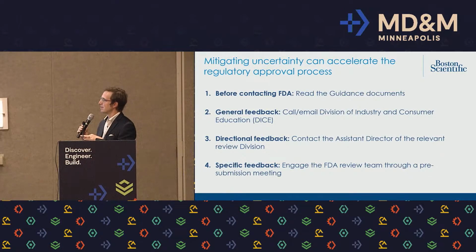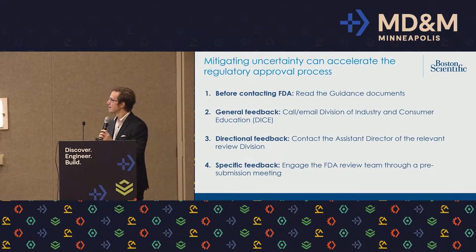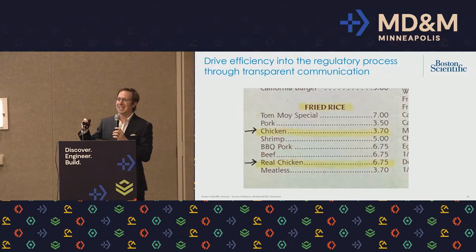And then for more specific feedback, engage the FDA review team through pre-submission meetings. And this is when you want more technical feedback on alignment on a specific test method or clinical trial design or animal study. Now, the pre-submission process isn't only helpful for sponsors, for the companies to get alignment on these strategies, but it's also useful for regulators because they're gauging through this interaction what they can expect from the sponsor.